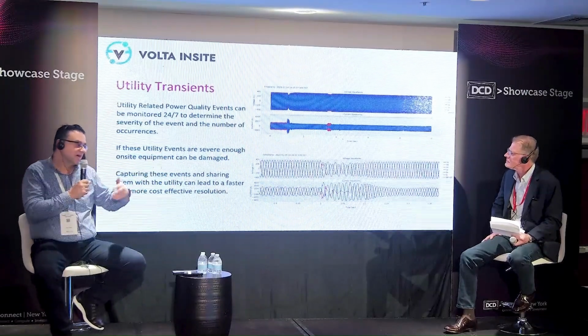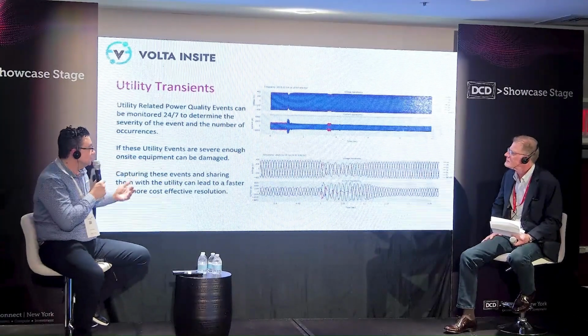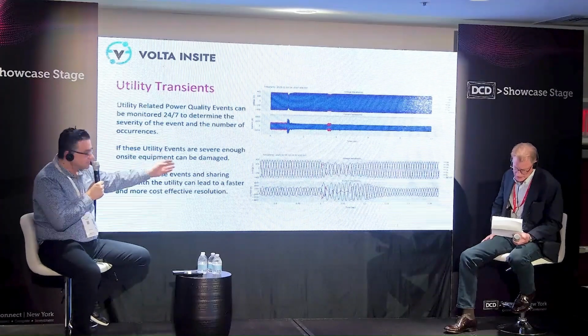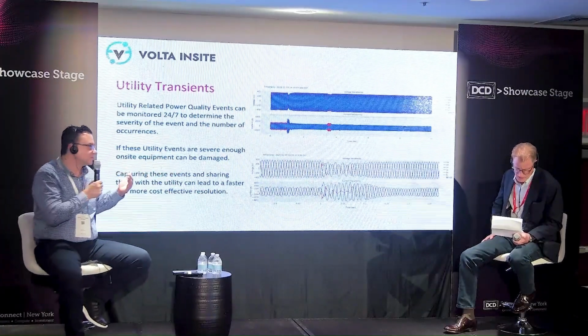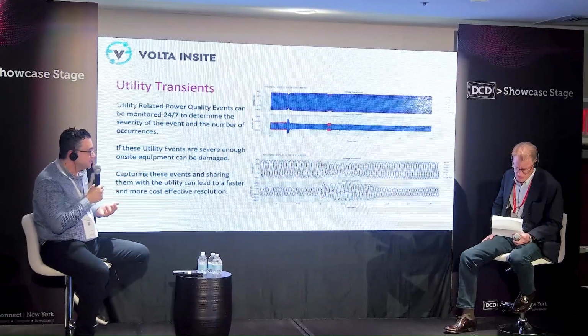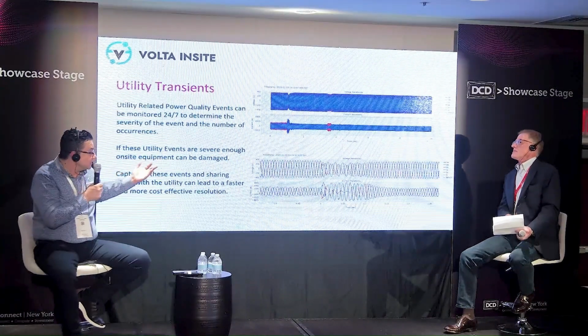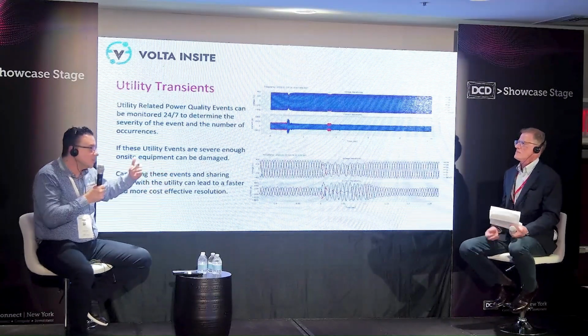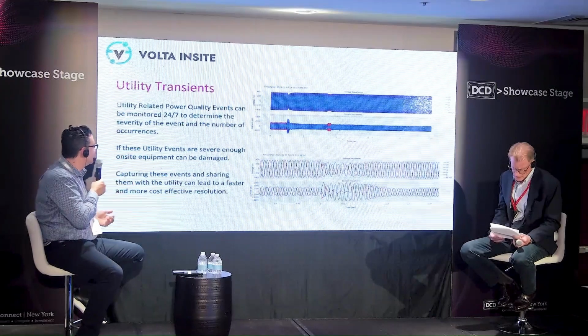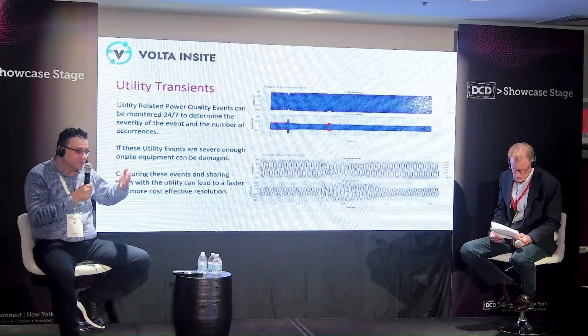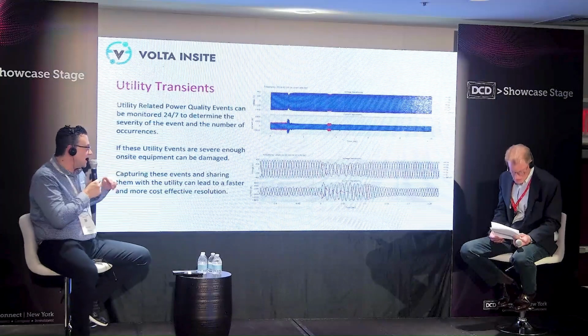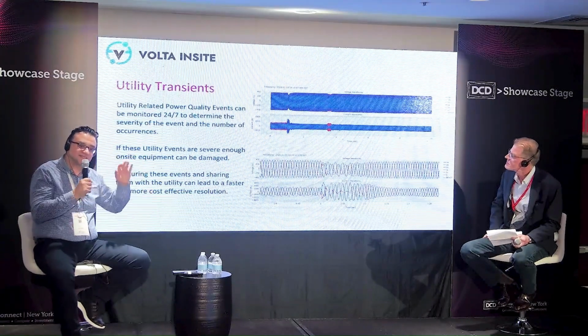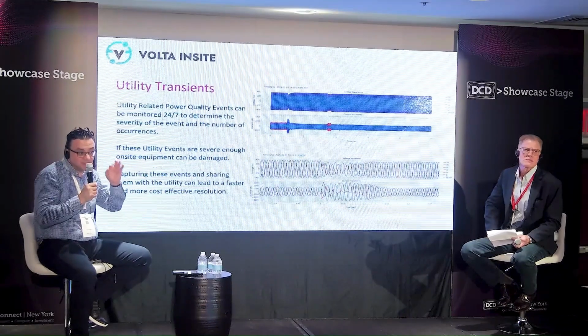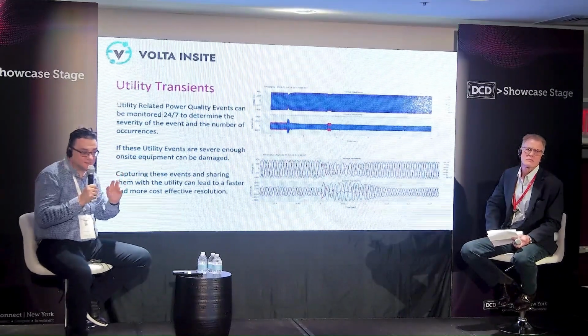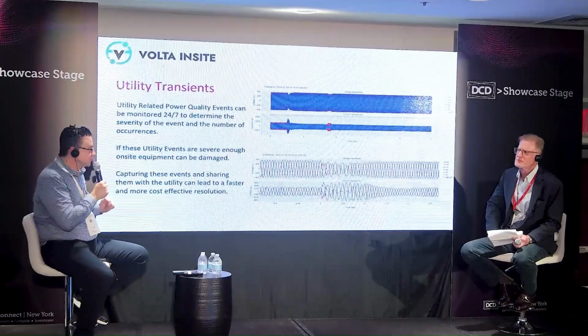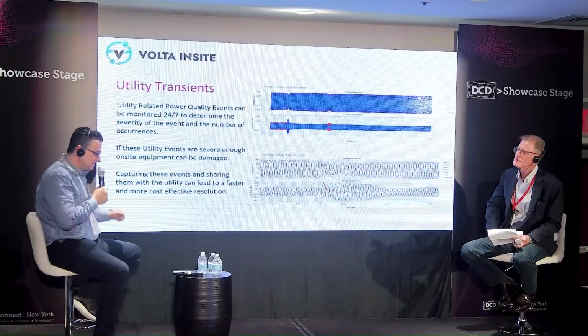Now, how does that translate to anything within a data center? That voltage variation may actually set off a rack, reset servers, or even affect your cooling system, like a motor kicking out from overloading. Because of our continuous monitoring and event captures, we're able to capture all of this and analyze it, giving some type of intelligence on the back end as to how it can potentially be addressed. So that's utility transient.